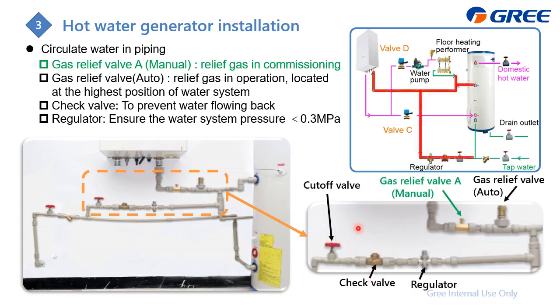And on this side, you need to install first the gas release valve A. This is manual. The purpose of it is just to release the trapped air in the commissioning stage. And the gas release valve, this one, is automatic. The purpose of it is also to release the air, but in the operation stage, and it is located at the highest position of the water system. And also this check valve to prevent the water from flowing back, and also a regulator to ensure the water system pressure is less than 0.3 megapascal.